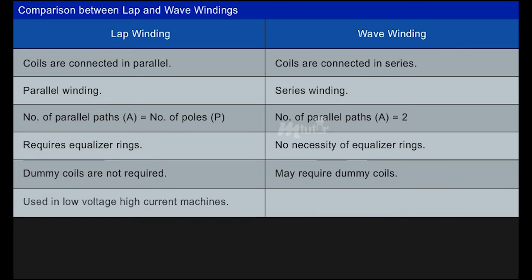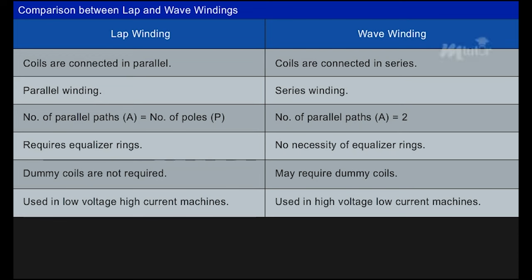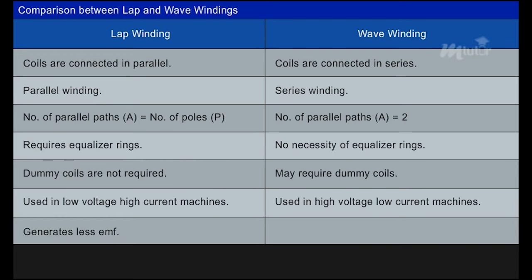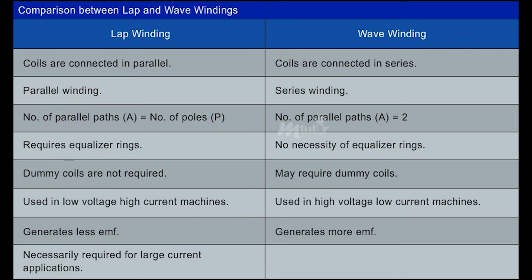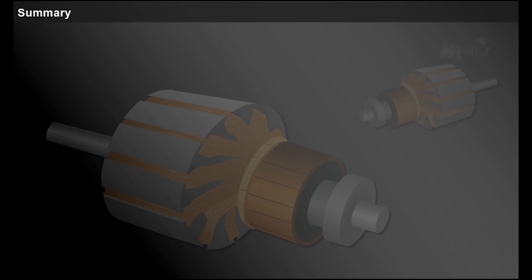Low voltage and high current machines use lap windings, but wave windings are used in high voltage and low current machines. Lap winding generates less EMF compared to wave winding. Due to more parallel paths, lap windings can be used for large current applications, whereas wave winding is not suitable for such applications as it has only two parallel paths.